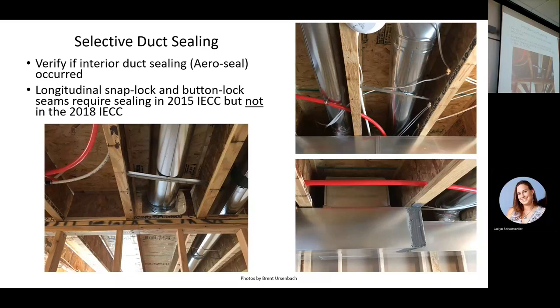Well, is this the AeroSeal, or is it the one that they do the whole house? Has anybody seen them do the whole house after drywall? Is this like for floor doors? Yes, they spray it all in the house. Well, they mask the windows so you don't seal them, but they set up these little tripods with these little misters, and then they pressurize the house to 75 pascals. Aero barrier. I think it's aero barrier. It's AeroSeal for the ducts and aero barrier for the house. So they spray this mist into the air with the house pressurized.